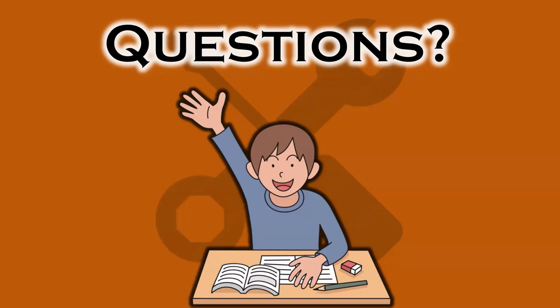It's a good question. Gotcha. Thank you. I have a couple questions. Is the humidity issue one of the reasons why Mitsubishi recommends, like how they always have the fan running on low speed? The fan always runs in a Mitsubishi unit primarily because by default we're using the return air temp sensor to control space temp. And if we're not moving air, we can't sense the space temp. Okay. Now that process of doing that can contribute to the humidity issue, because any moisture that condensed on the coil gets pushed back in the air.